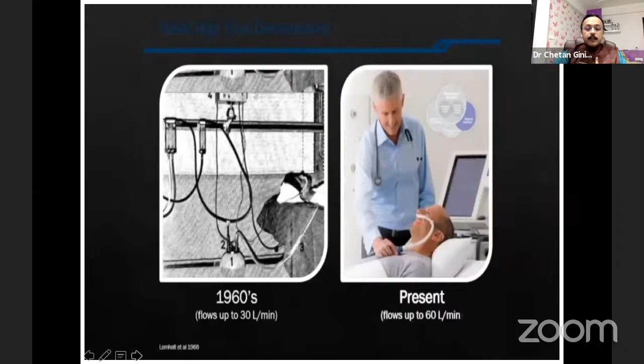There is reduction of the overall dead space. The anatomical dead space extends from our nostrils to the nose, nasopharynx, pharynx. Then comes the trachea and the main bronchi. And then it divides into almost 30 generations of airways before it reaches the respiratory bronchiole, where the gas exchange actually starts. Now, when the child is in distress, we would want to deliver as much oxygen concentration as possible, and also remove the carbon dioxide in this anatomical dead space, which is not taking part in gas exchange. By using high flow as such, which is flows exceeding around 2 liters per kg, we are able to wash away this anatomical dead space and replace the dead space by fresh gas, which is also heated and humidified.